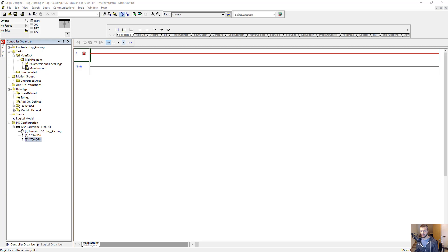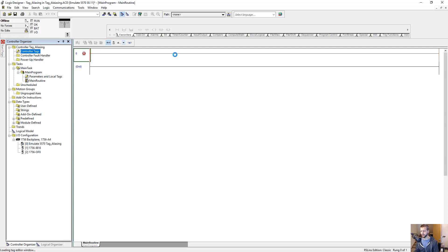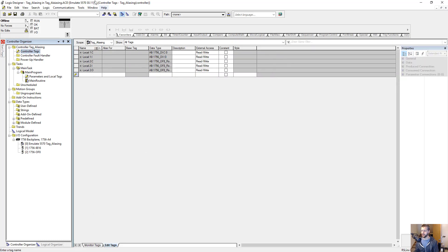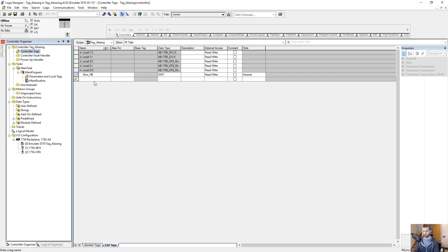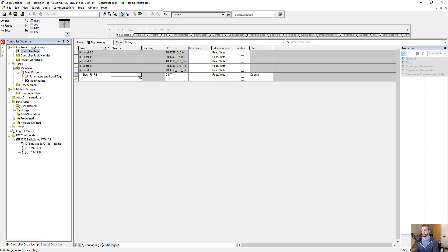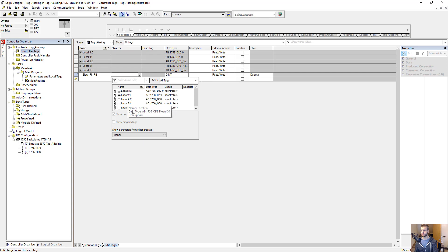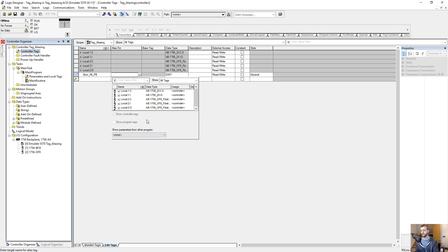Let's go ahead and create two new tags for our push buttons. We'll go to the controller tags folder and add new tags. The first tag we're going to call slow fill PB for push button. This is where the aliasing comes in — if you select this field, you can see all the other tags in your system and choose one. Tags are created for each input and output module. We have discrete inputs in local 1, which is our slot 1 module — the IB16. Local colon 1 colon I is the inputs of the local chassis slot 1.